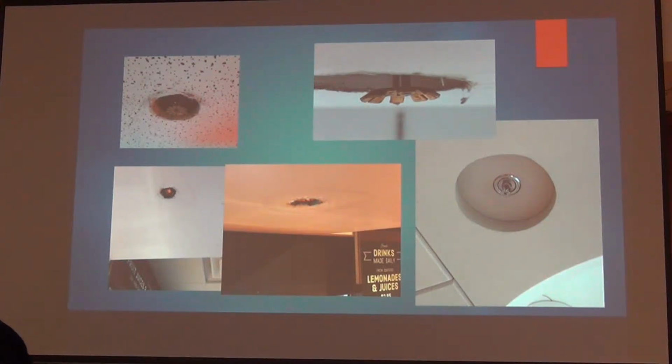How do they adjust that? Channel locks. Oh, right there. Channel locks, lowering the rod, or putting on one of these specialty fittings. They come in 1/2 and 3/4 inch length, and they're UL certified, NFPA approved to put on there and extend it down. Most of the time, you'll get it extended down 1/2 inch so that you get your deflector height.